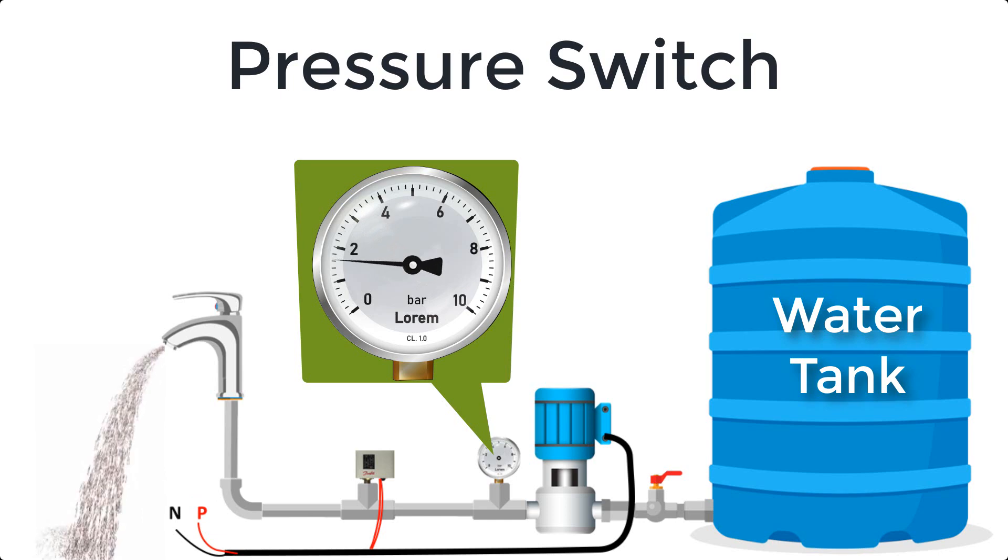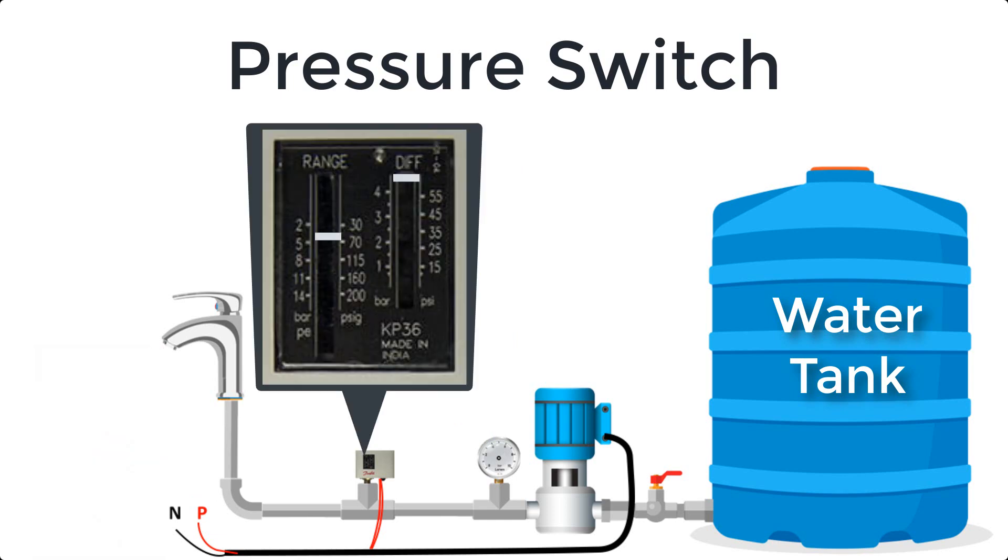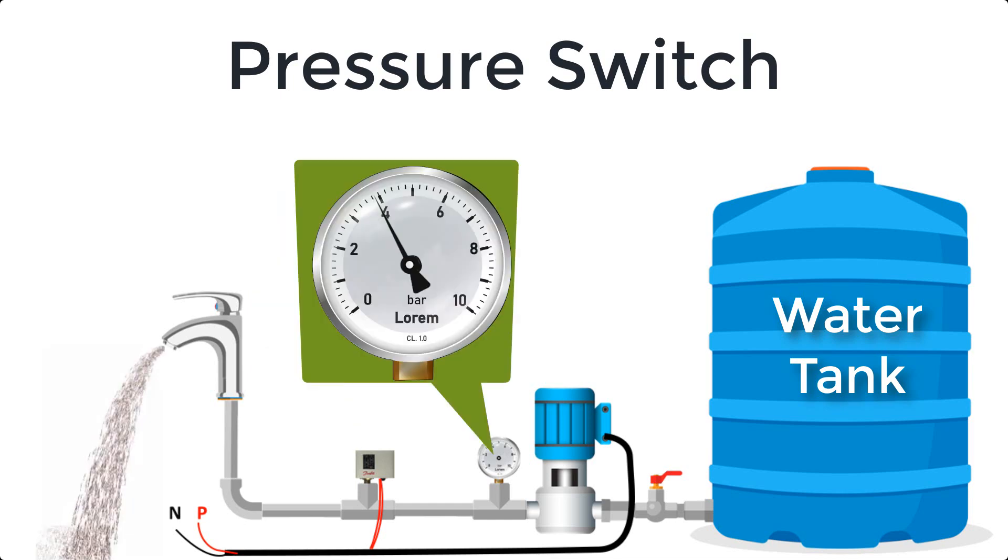When someone opens water tap, pressure will go down. So we have to adjust settings at what pressure the pressure switch should reset and pump turn on again. If we set difference at 1.5, it means when pressure reduces 1.5 bar, pump will turn on. Or we can say when pressure goes at 2.5 bar, pump will be turned on.